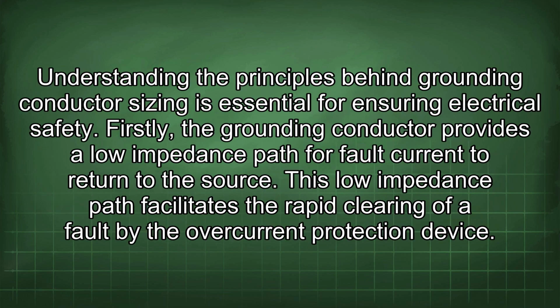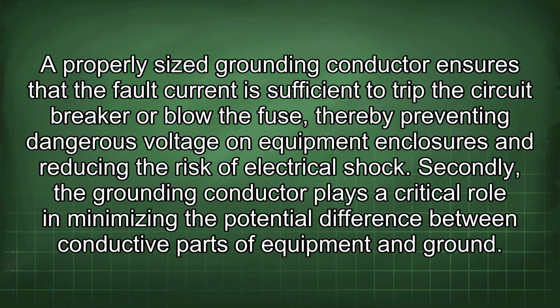Understanding the principles behind grounding conductor sizing is essential for ensuring electrical safety. Firstly, the grounding conductor provides a low impedance path for fault current to return to the source. This low impedance path facilitates the rapid clearing of a fault by the overcurrent protection device. A properly sized grounding conductor ensures that the fault current is sufficient to trip the circuit breaker or blow the fuse, thereby preventing dangerous voltage on equipment enclosures and reducing the risk of electrical shock.